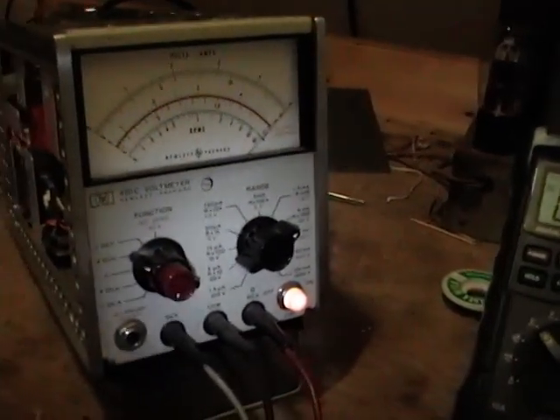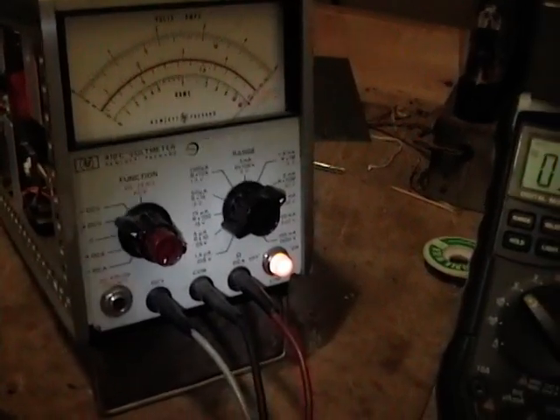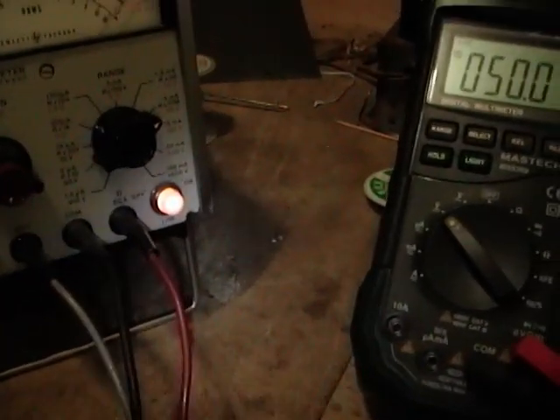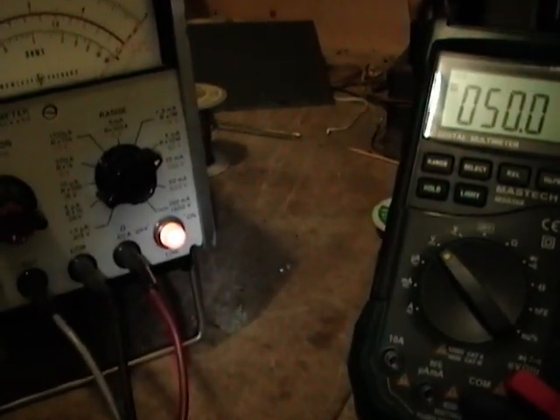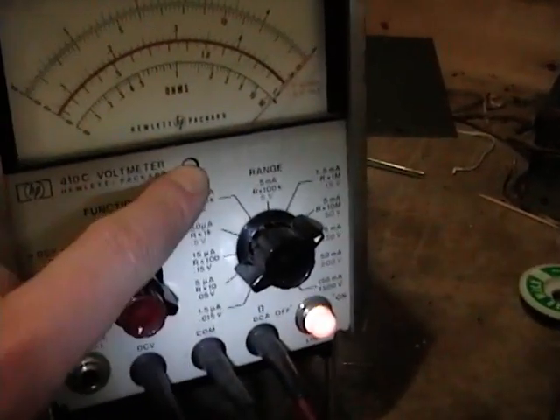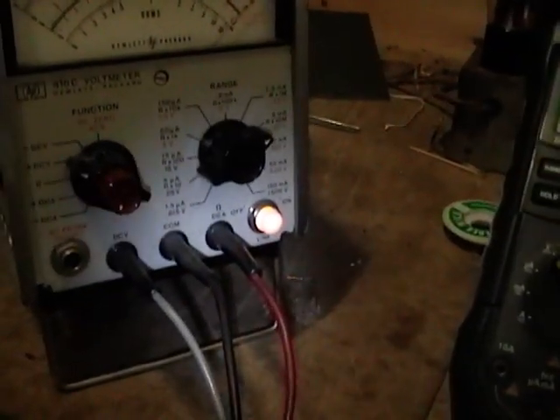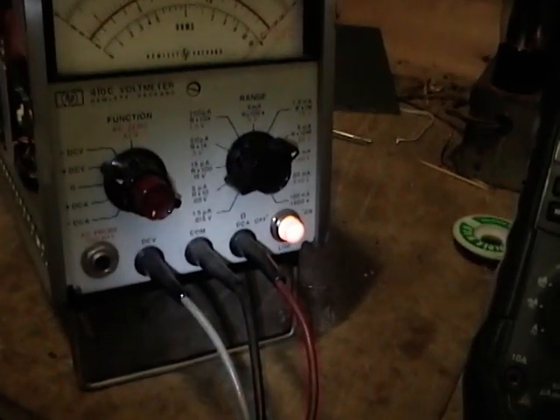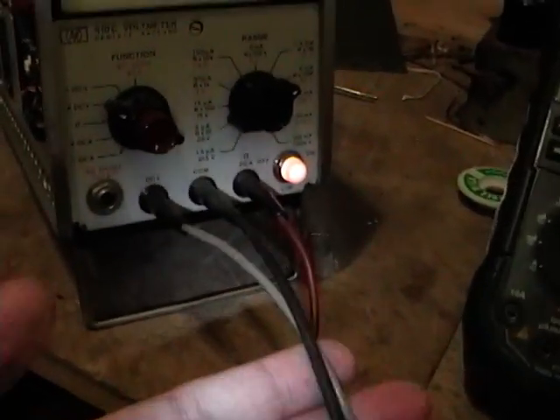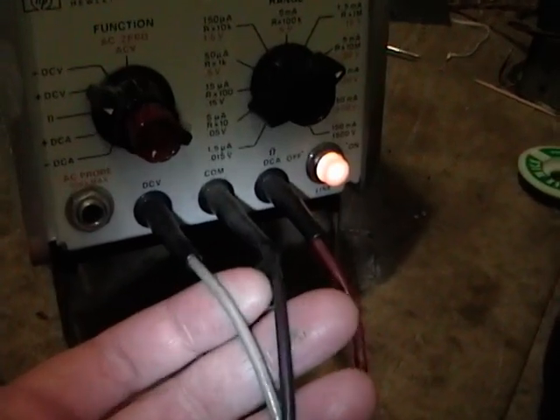The calibration procedure for the DC range is fairly simple. First thing is you turn the meter off, and you adjust this mechanical adjustment to get the needle right on 0. Turn it on, wait about half an hour for it to warm up. Short the DC V connector and the common together. And there's an adjustment on the back for 0 adjust, so tweak that so the needle is dead on 0.